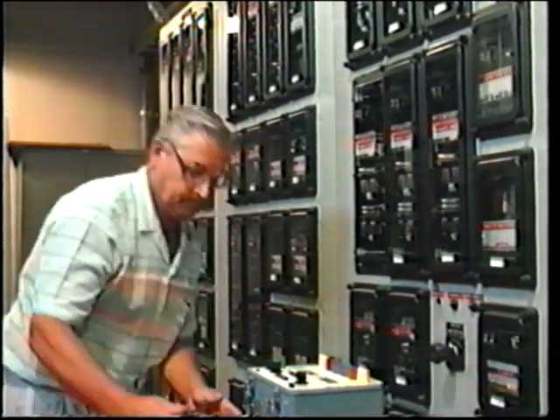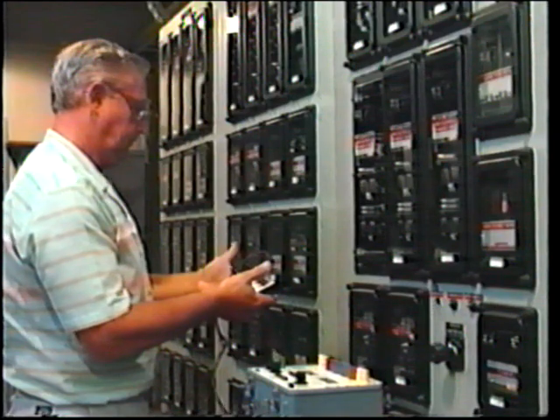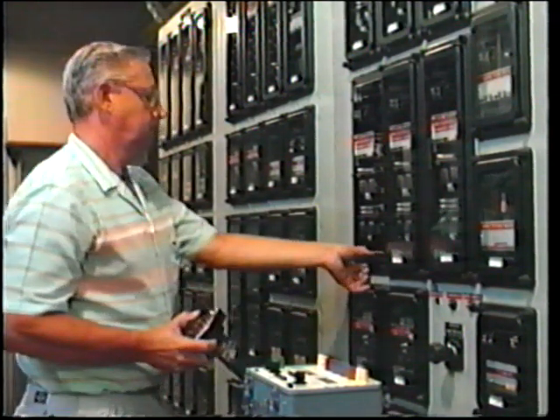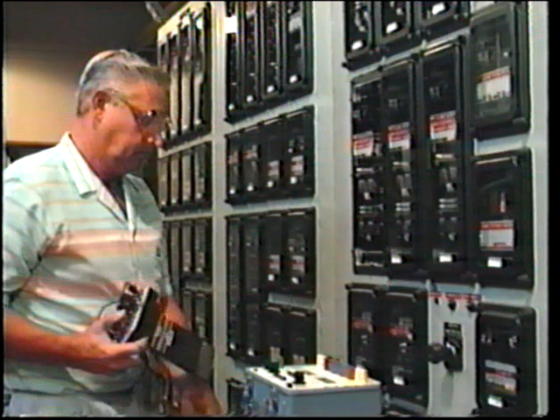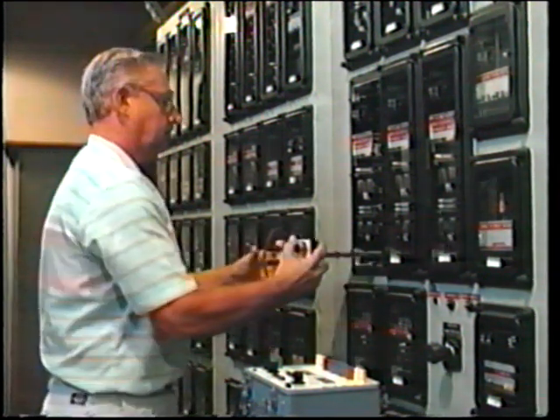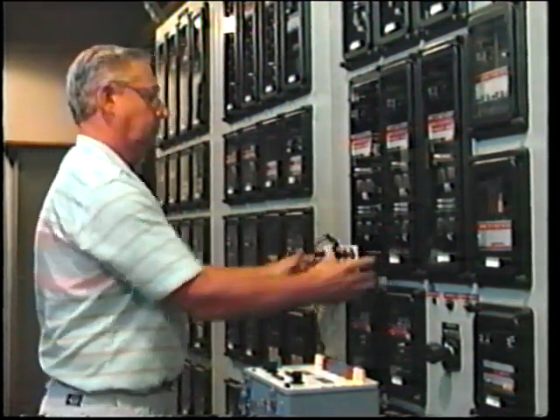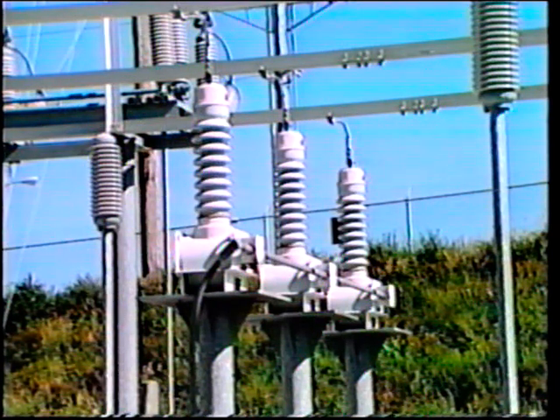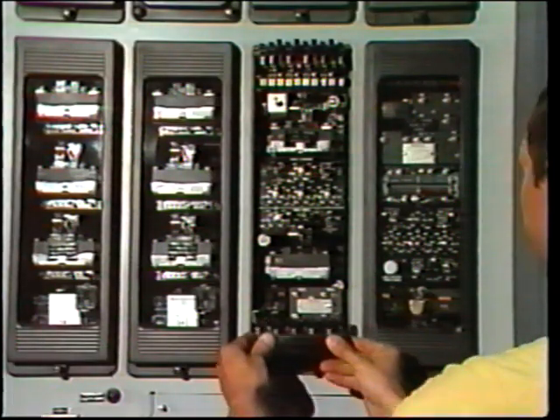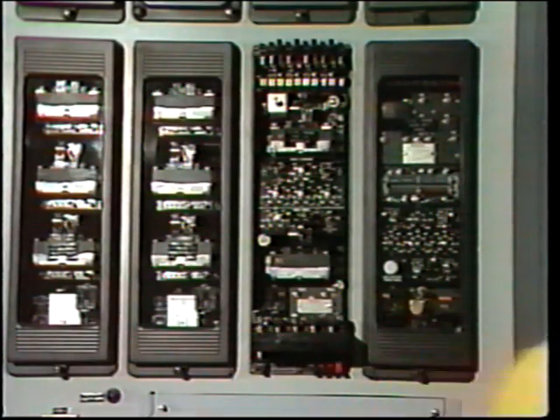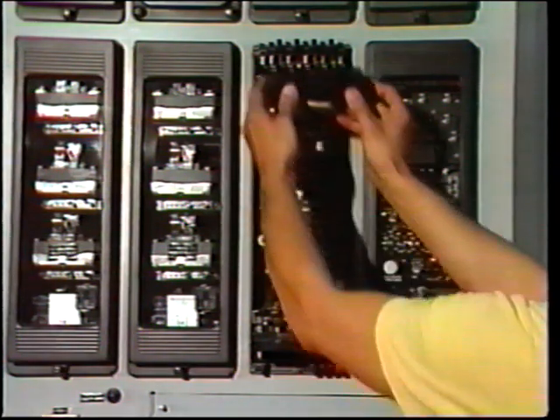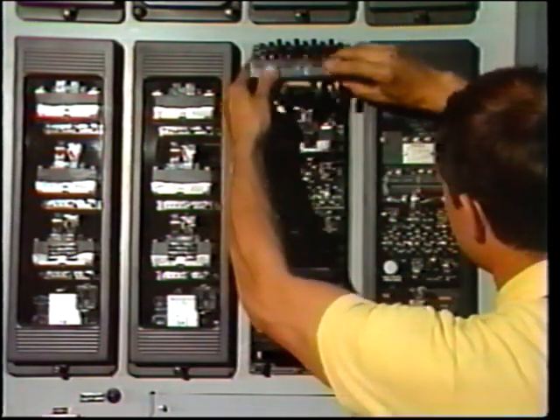In-service testing may also be required at times other than routine testing, for example, during troubleshooting. In-service tests are also performed to measure current and voltage on relays during normal operation. This serves as a check on the measuring circuits, CTs, and VTs. As the technician must access live relays, we have to face the possibility of inadvertent tripping. Clearly, great attention must be paid to both preparation and performance of in-service tests. Most companies lay down guidelines and procedures to cover this activity.